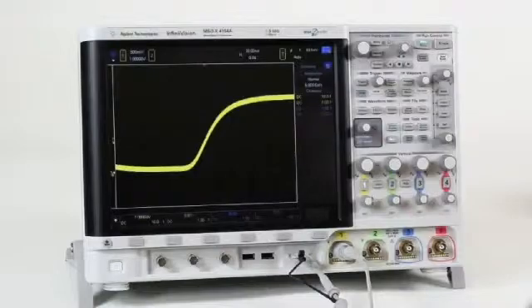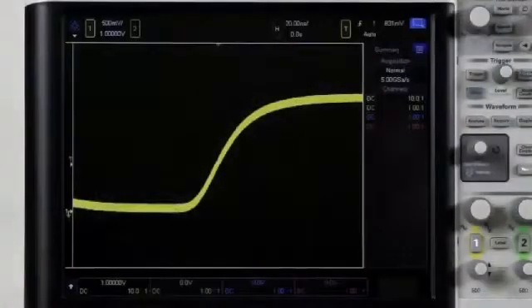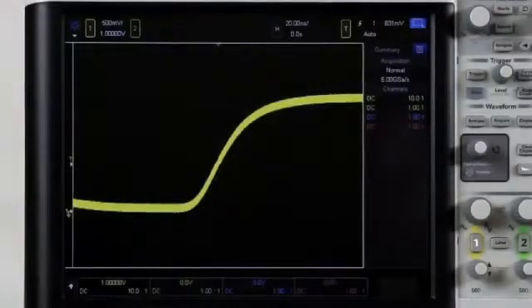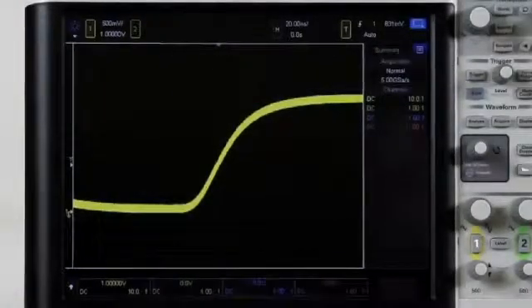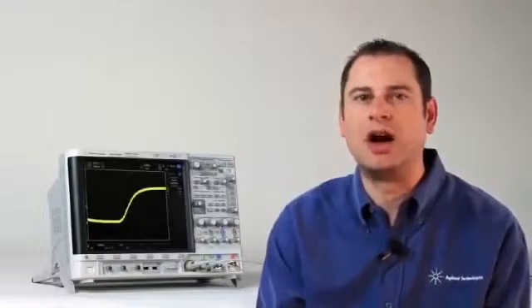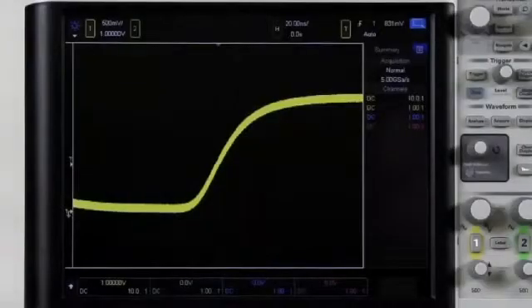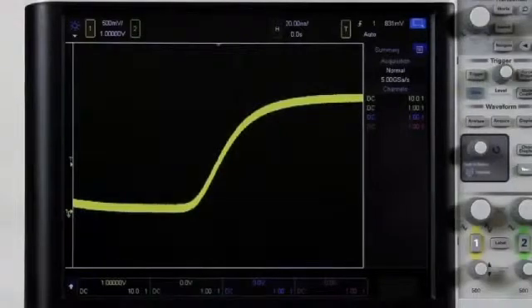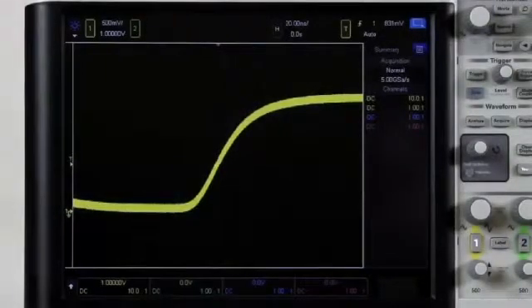One of the benefits of a very fast update rate like the 4000X's is it greatly increases your likelihood of capturing infrequent events. Infrequent events are so challenging to debug because by definition, they are rare. As you can see on the screen, we have a very intermittent glitch happening on our test signal.